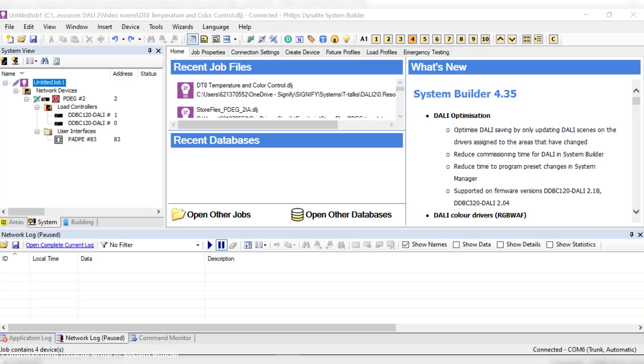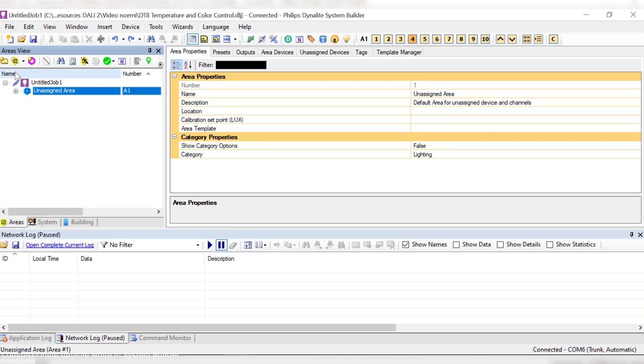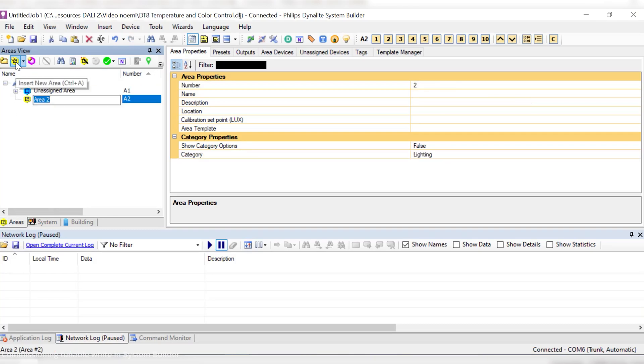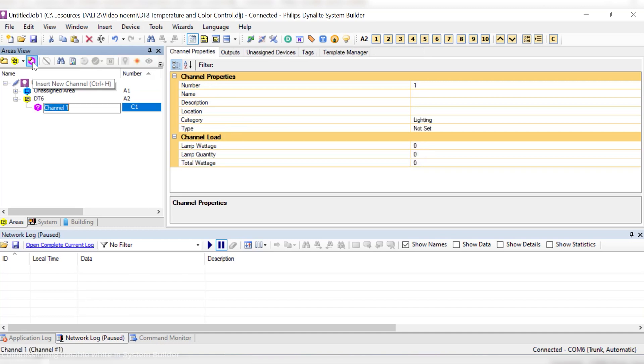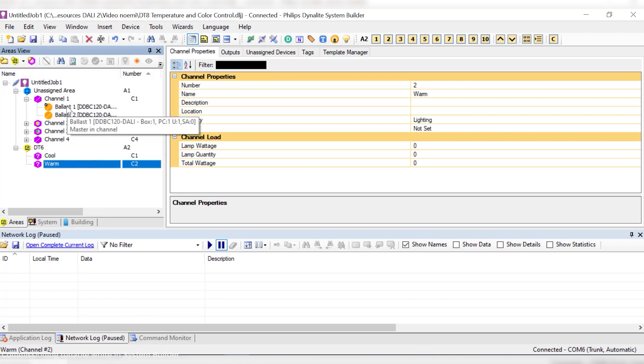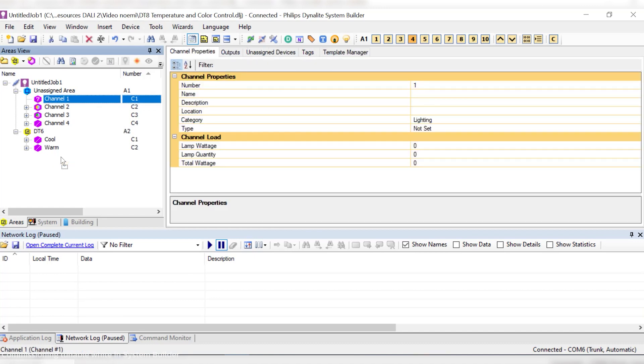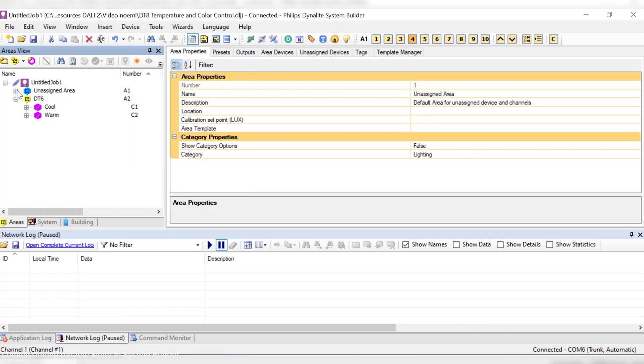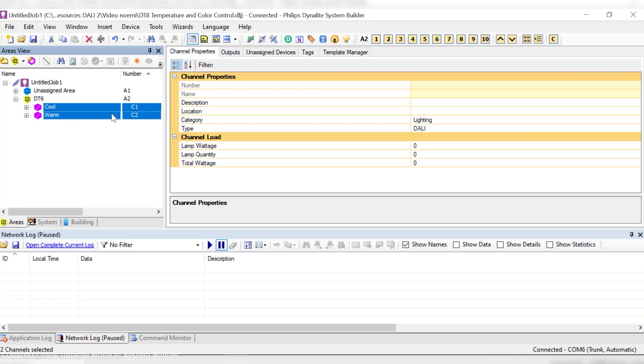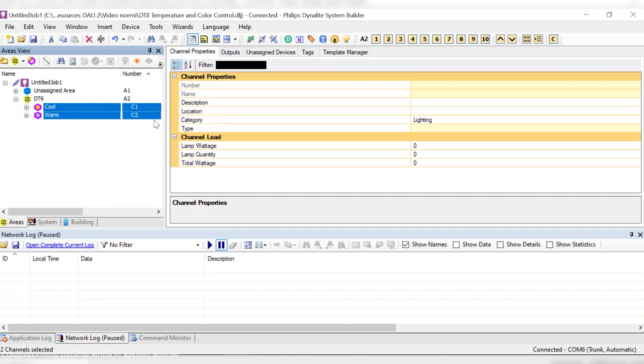So here we have a simple Dynalite project where we can find an Dynet gateway also known as PDEG, two DDBC120-DALI which is our one universe DALI-2 certified controller and a keypad, in this case the Antumbra display. I'll show you two examples on how to add DALI channels. First, I'm going to create an area for standard LED drivers which can also be referred to as DT6. In this case, tunable white will require two drivers, one for cool white and another one for warm white.